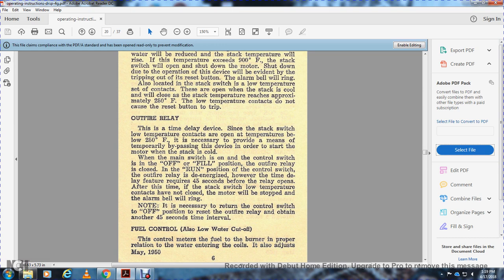When the main switch is on and the control switch is in the "OFF" or "FILL" position, the outfire relay is closed. With the control switch in the run position, the outfire relay is de-energized. However, the time delay feature requires 45 seconds before the relay opens. After this time, if the stack switch low temperature contacts have not closed, the motor will be stopped and the alarm bell will ring. Note: if necessary, return the control switch to the off position. Reset for the outfire relay is obtained after another 45-second time interval.